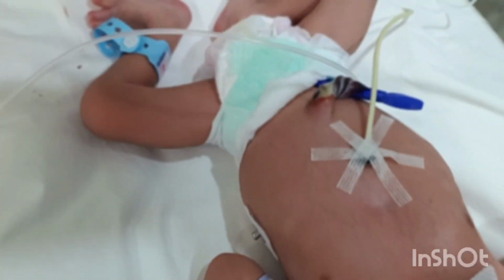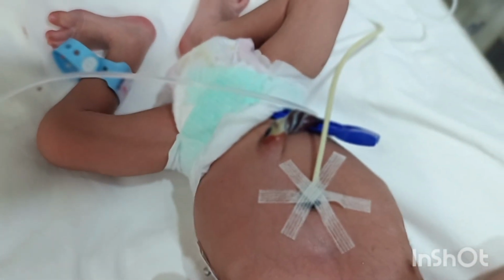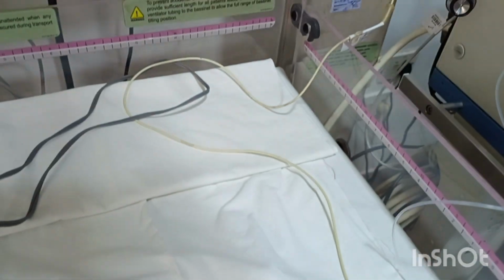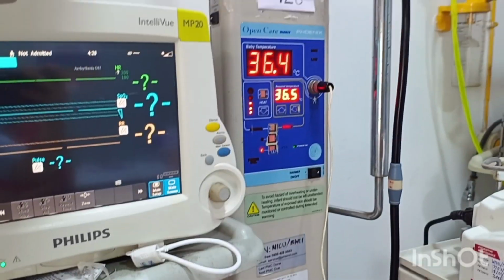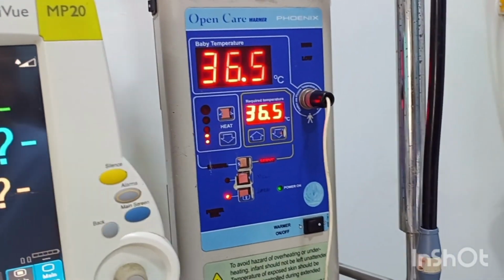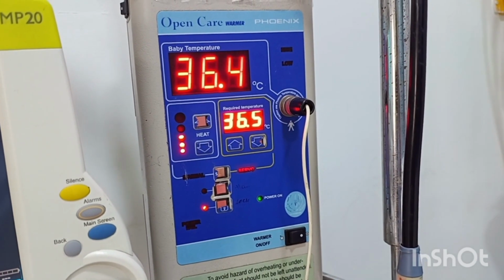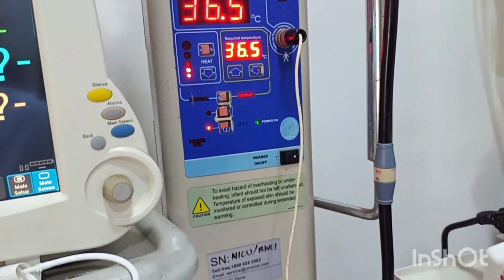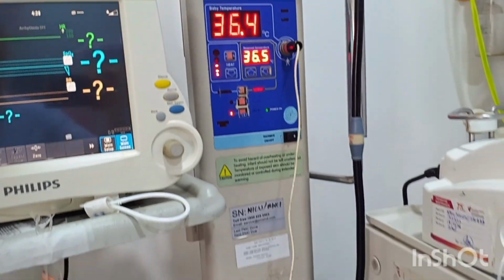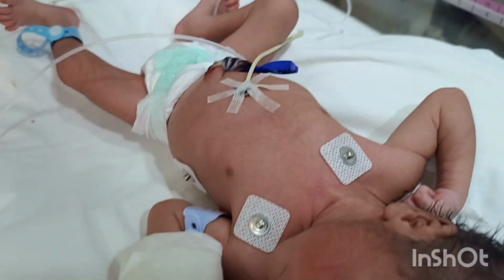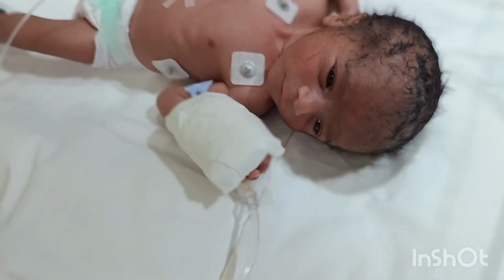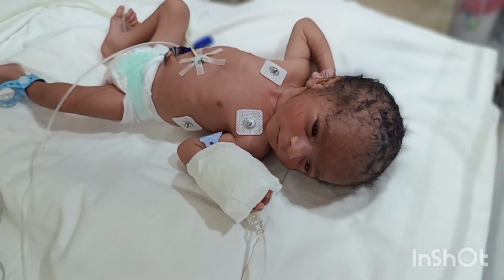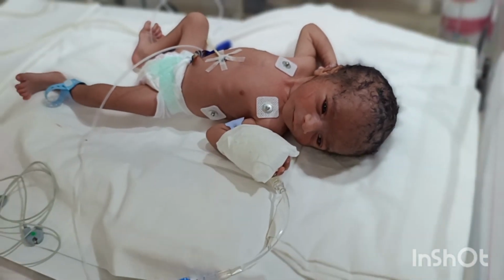Now there is a third probe. This is the temperature probe of the radiant warmer, which is fixed on the baby's abdomen, and it has to be fixed firmly because the baby's temperature is constantly being monitored by the machine and the heat is delivered accordingly. Here we have put 36.5 and the baby is also 36.5. So the baby is in a thermoneutral environment, comfortably lying on the radiant warmer.